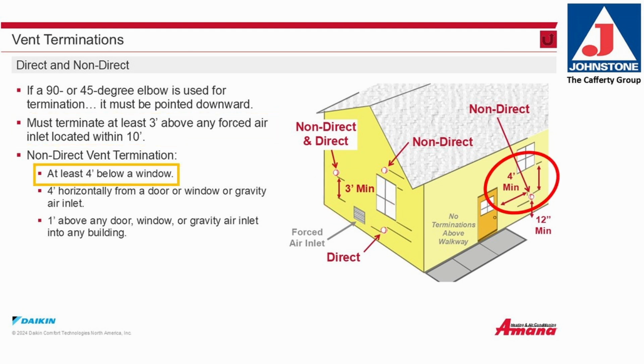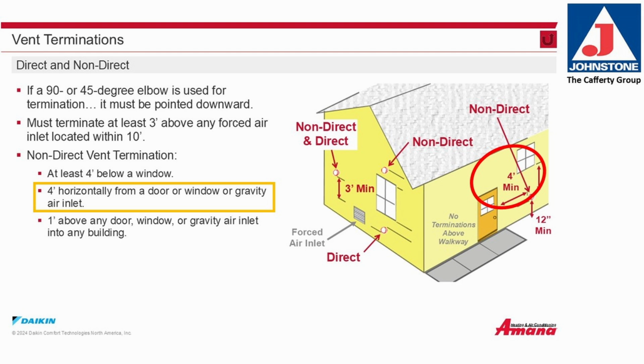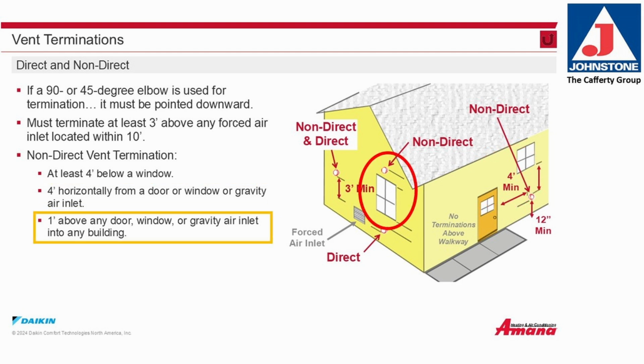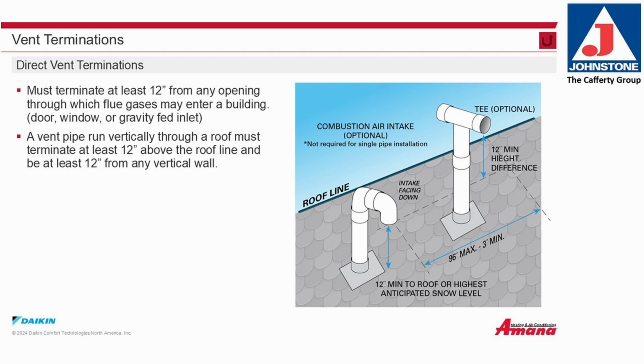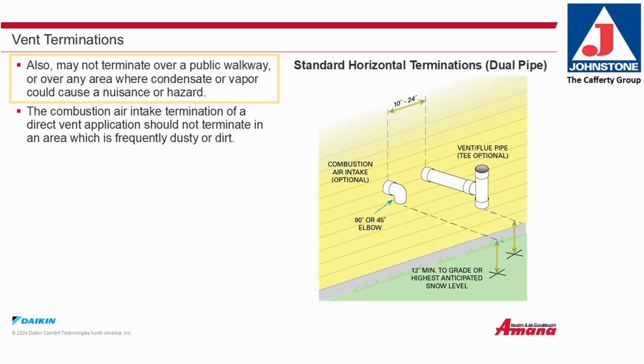Non-direct vent termination: at least 4 feet below a window, 4 feet horizontally from a door, window, or gravity air inlet, and 1 foot above any door, window, or gravity air inlet into any building. Direct vent terminations must terminate at least 12 inches from any opening through which flue gases may enter a building, door, window, or gravity-fed inlet. A vent pipe run vertically through a roof must terminate at least 12 inches above the roof line and be at least 12 inches from any vertical wall. Also, it may not terminate over a public walkway or any area where condensate or vapor could cause a nuisance or hazard. The combustion air intake termination of a direct vent application should not terminate in an area which is frequently dusty or dirty.